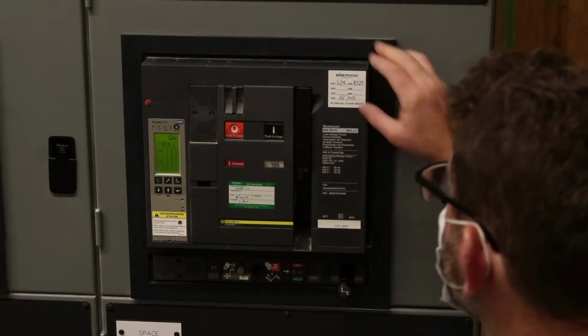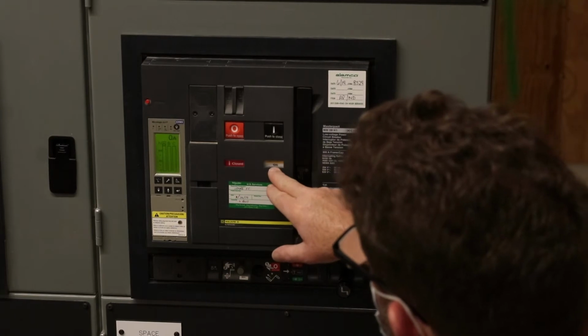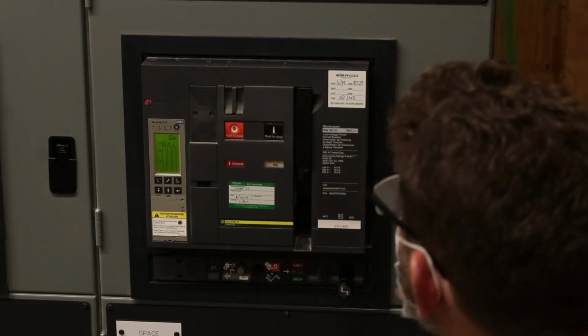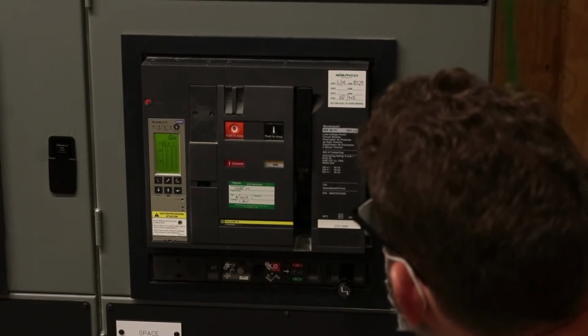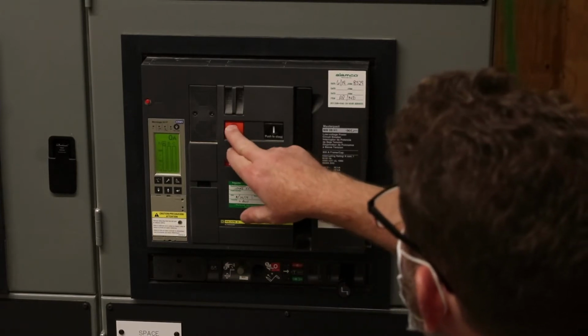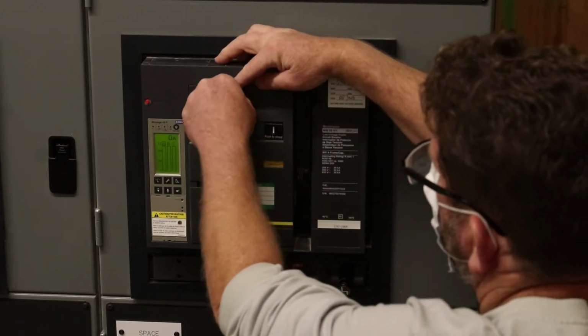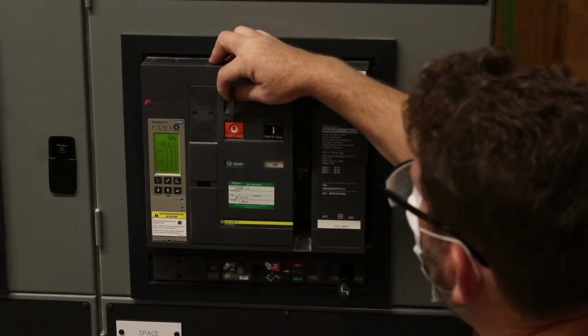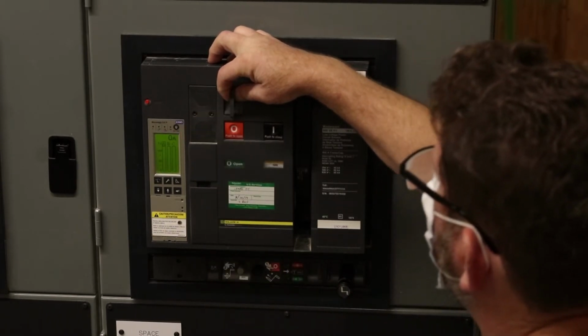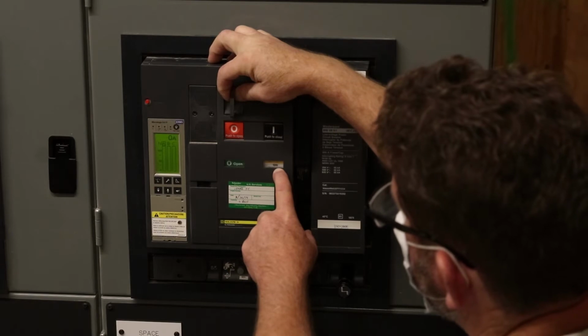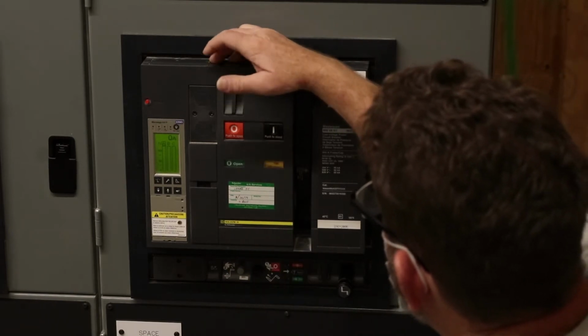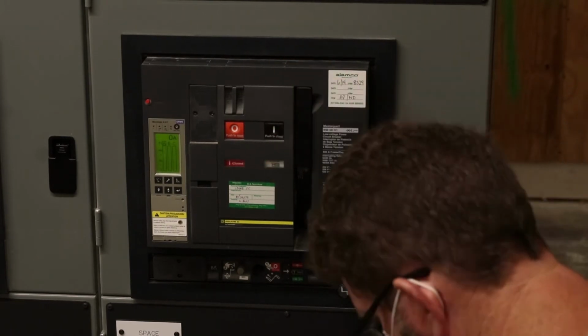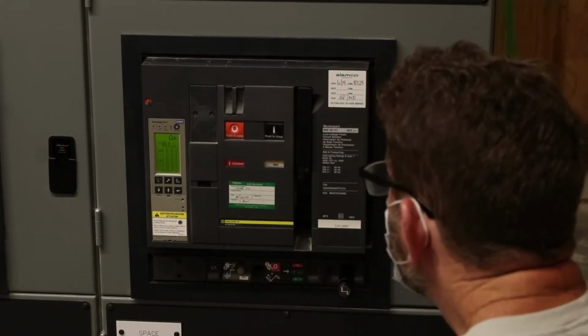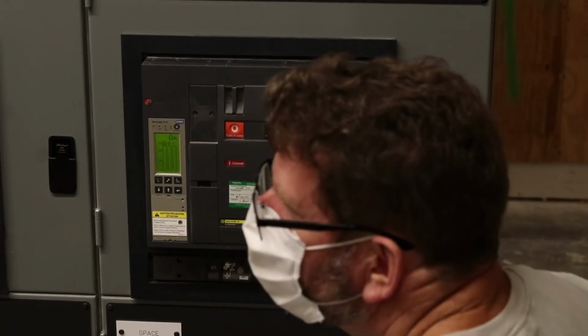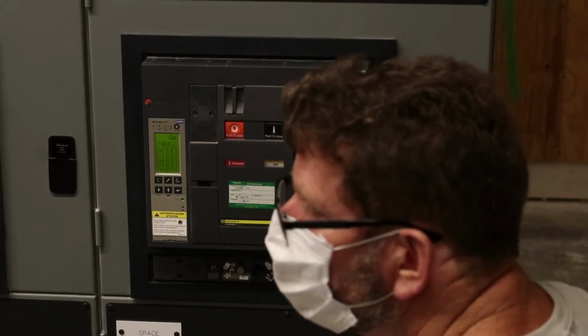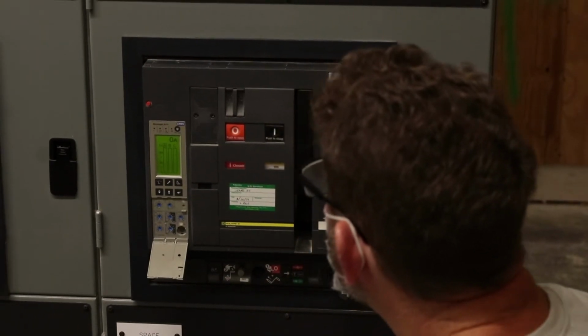Closing. Okay, now it's closed, not okay. Or charged, not okay. Opening. Padlock attachments here. If you're doing lockout tagout for the downstream loads out of this, you just put your lockout tagout lock there. Notice when I pulled it out, it goes charged, not okay. Closing. It says 6, but it might be 6 or 7. Okay, now we're closed.